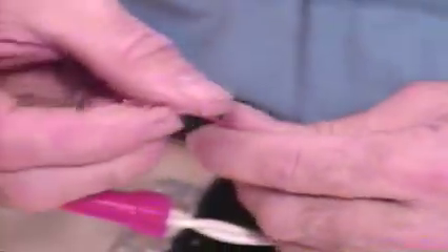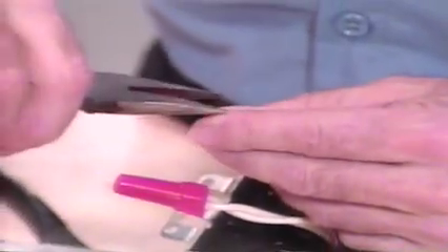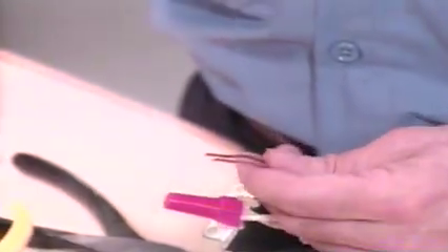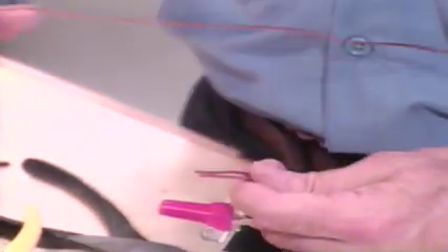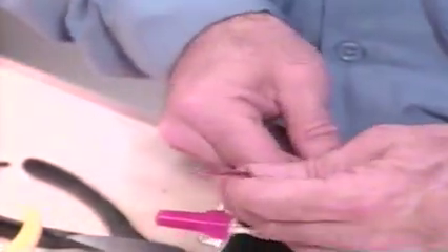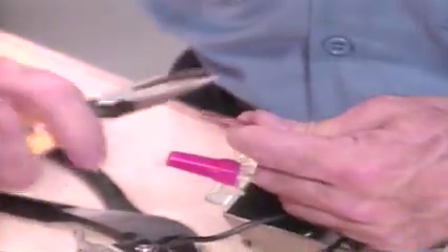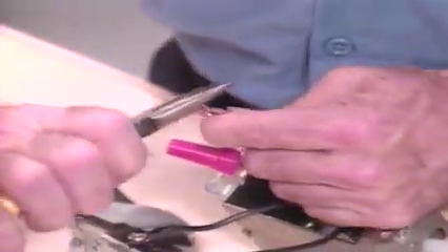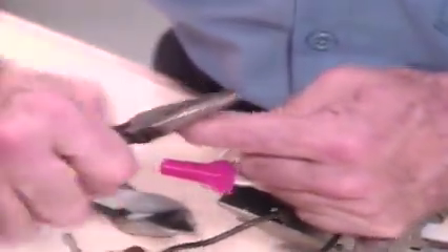And the ground wires? The ground wires also have to be twisted together, but they also need to be grounded to the box. How are you going to do that? With a pigtail. Pigtail? Of course. Cut a little short piece of bare wire, twist the 3 together. All right. Clockwise, of course. Wire nut them together. Voila! Pigtail. A pigtail. Colorful terms in the electrical business.